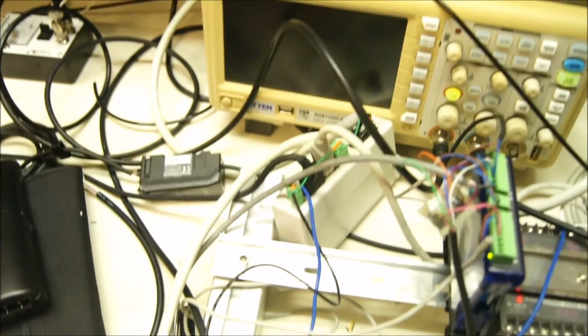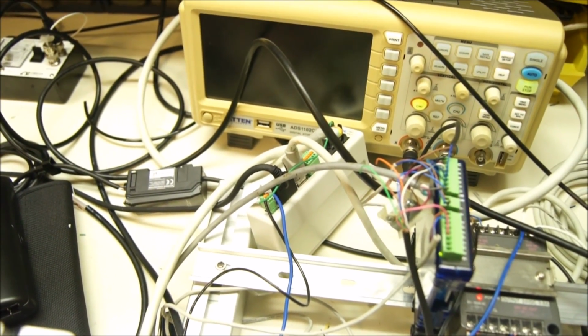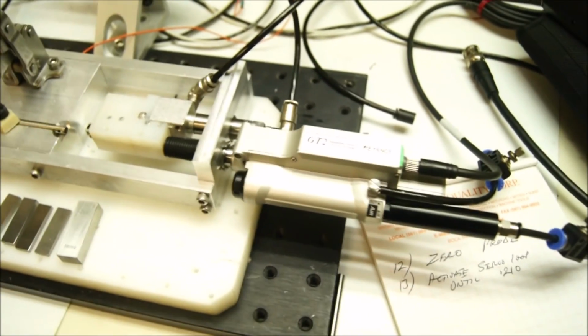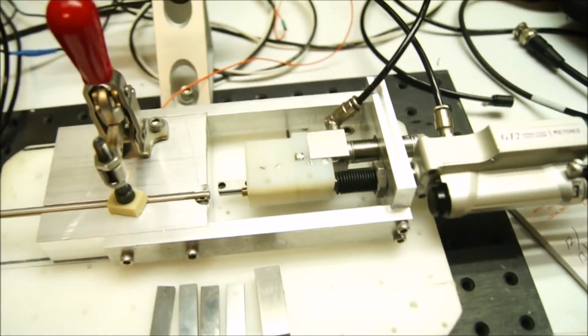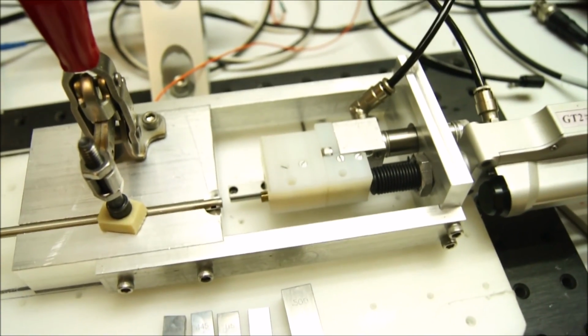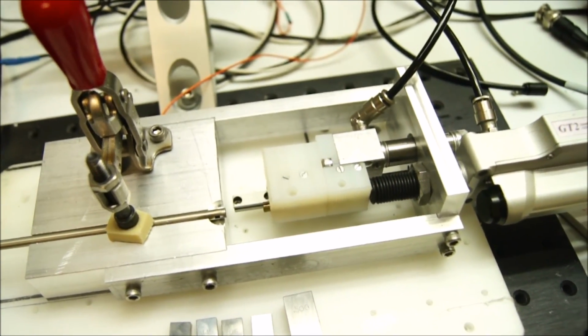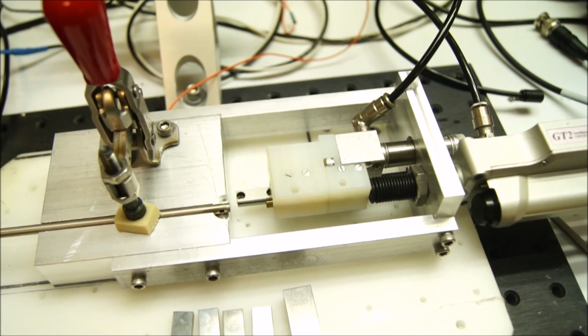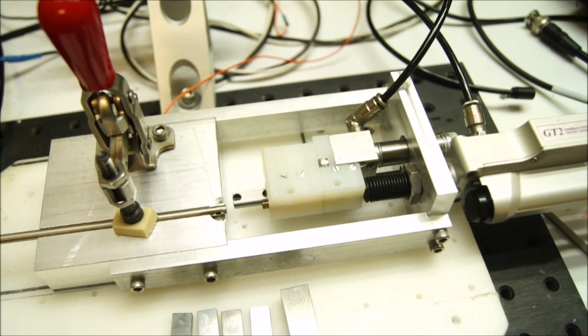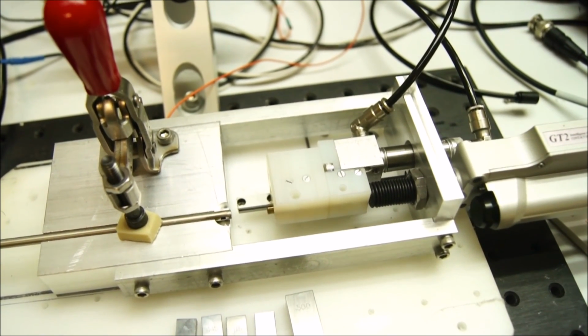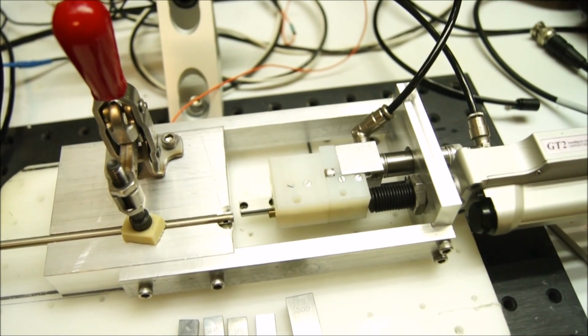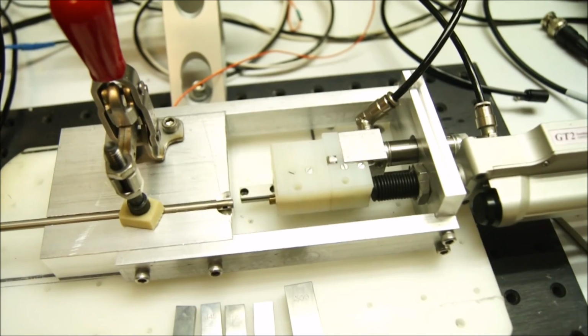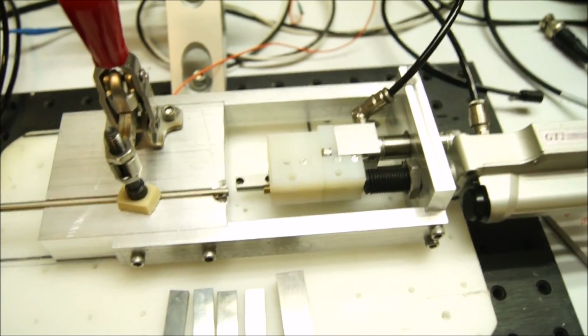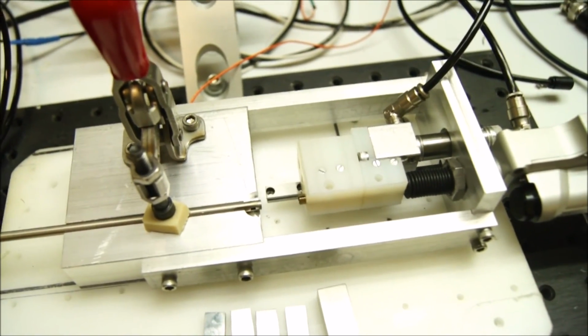Back here we have the signal conditioner for the linear encoder, the controller for the linear servo, and through this is the linear encoder. It's going to make the measurements. And here we have the compound probe. This probe will allow the measurement of the pusher in the beginning to the 0.210 distance distal of the cannula, and also it'll allow us to set the clip by referencing the rails and detecting when the clip is in the right position.